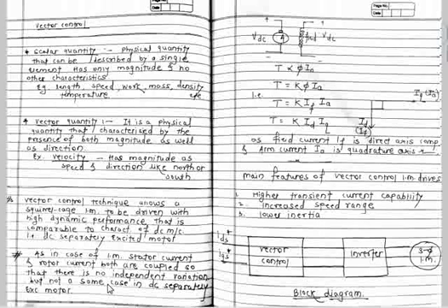So here we are saying that in case of the induction motor, stator current and rotor current both are coupled. It means that if I wish to change the magnitude of the stator current, there is a change in the rotor current. It is due to the slip present in the air gap, obviously in the induction motor. And if I wish to change the rotor current, there is a certain change in the stator current. So it means that the torque and the flux are both coupled to each other. One will give the variation in the other and vice versa. So how is vector control of an induction motor analogous to the DC separately excited motor?